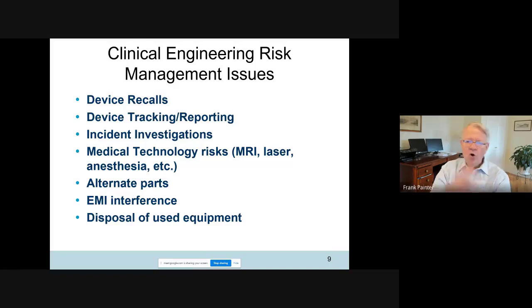Electromagnetic interference is the electromagnetic radiation one device gives off from its electronic circuitry that might interfere with another one. We have this problem in the operating room where an electrosurgical device, which cuts, it's a knife, but it's an electronic knife, and it generates a very high frequency current, and that electronic circuit board is radiating this electromagnetic interference into the environment, and the bedside monitors, if they don't have the right filters, or if the electrosurgical unit is not shielded appropriately, one device interferes with another.